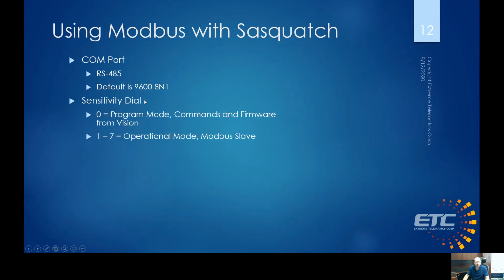Then as well, what's important is you've got to set up the sensitivity dial. If you're on 0, this COM port acts as a programming port with Vision. So you can change its mode, you can send it commands, update its firmware, those kinds of things. When you're in an operational position, such as 1 to 7 on the sensitivity dial, it acts as a regular Modbus slave. So you can use it with any Modbus master program to access the configuration registers and the logs.